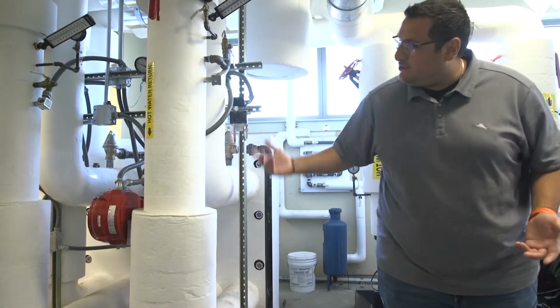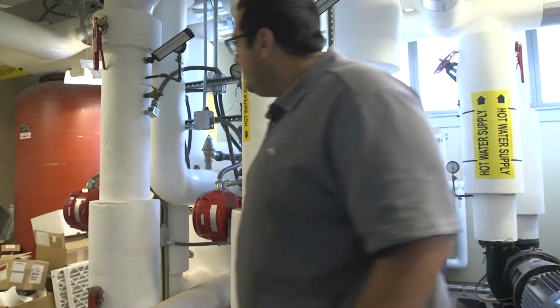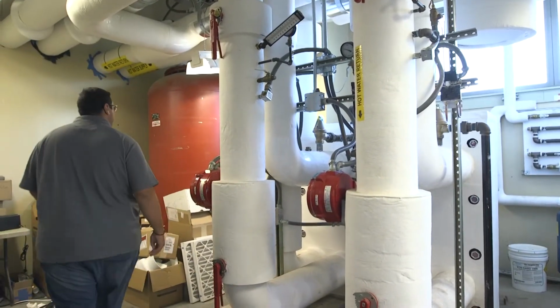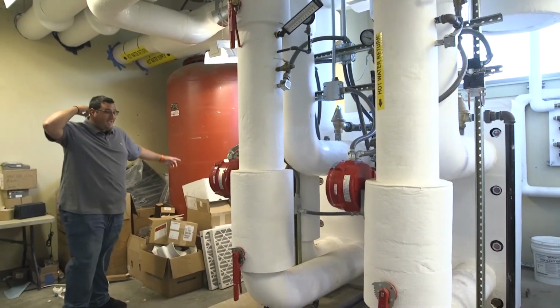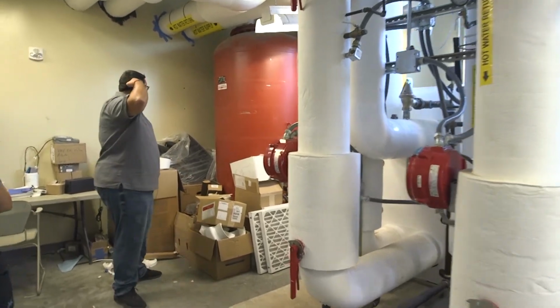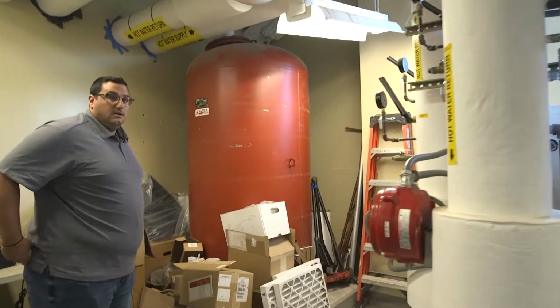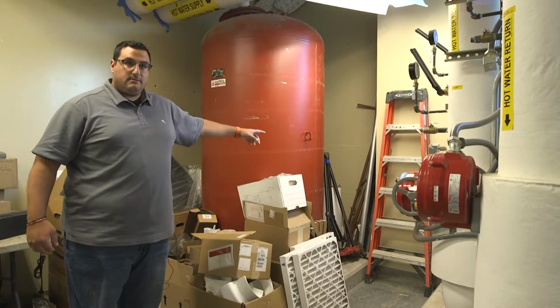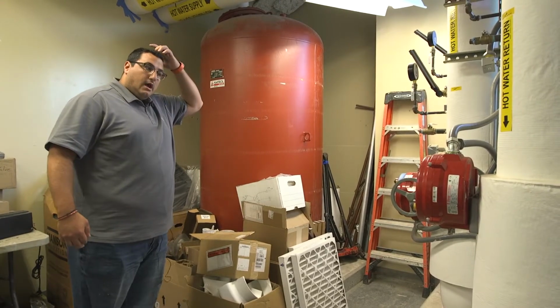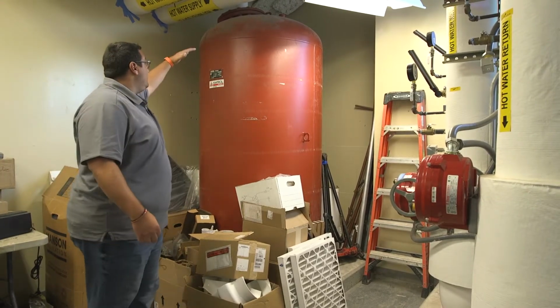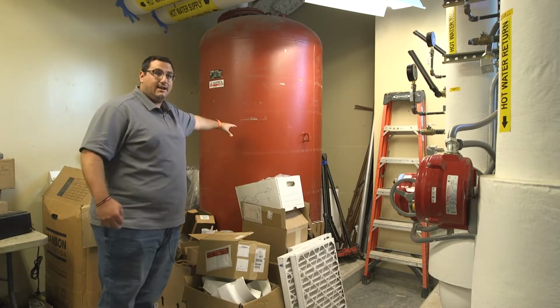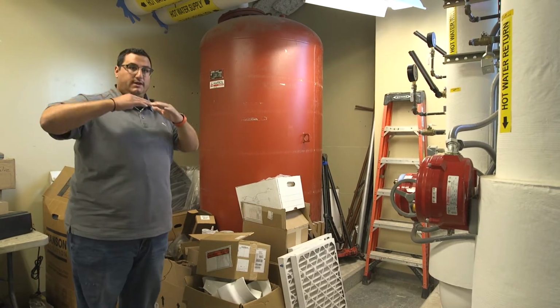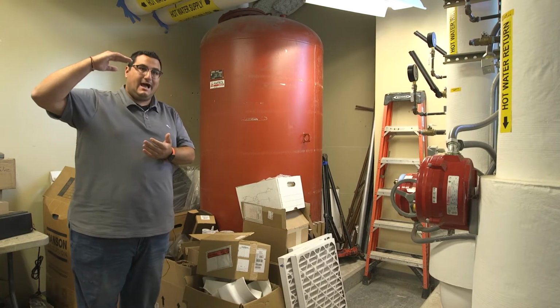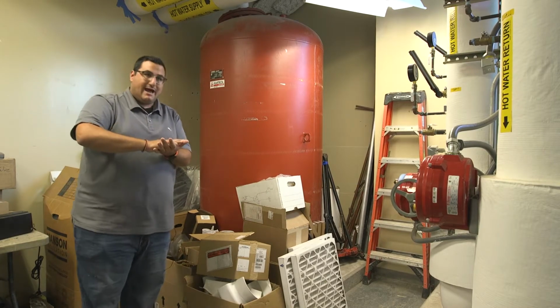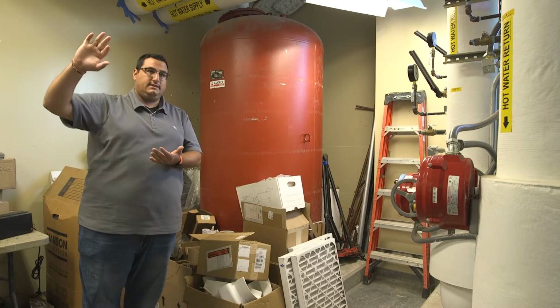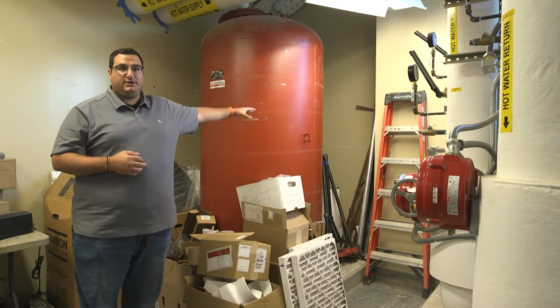And then what? There's an expansion tank, right? So this is your expansion tank. Inside you have a rubber bladder. The rubber bladder holds the water, and on top there's compressed air. When this was set, it was supposed to have a set point of a certain psi of air on top to squeeze the bladder down, which causes the water to come into the system. This keeps constant pressure in your system.